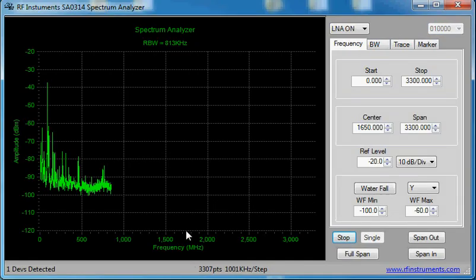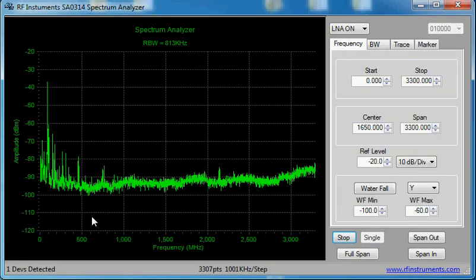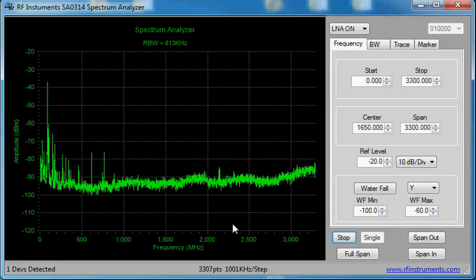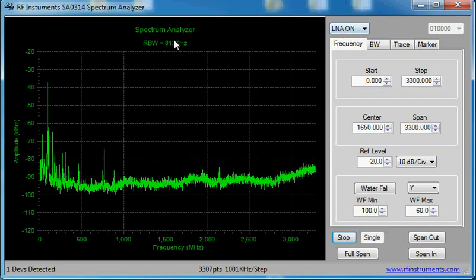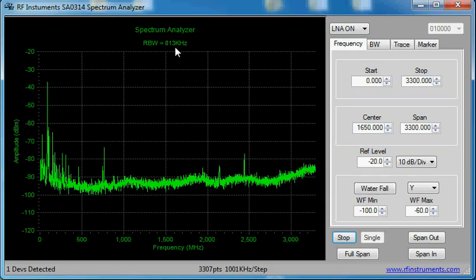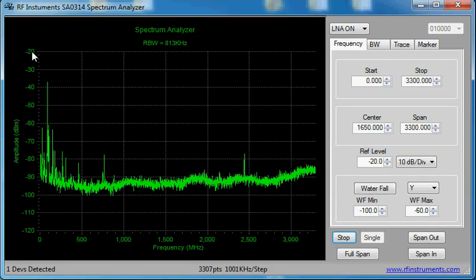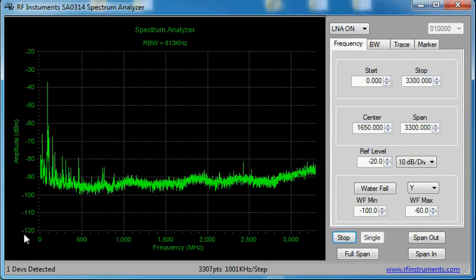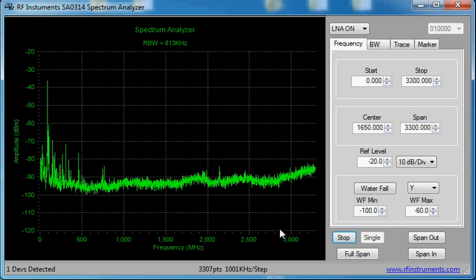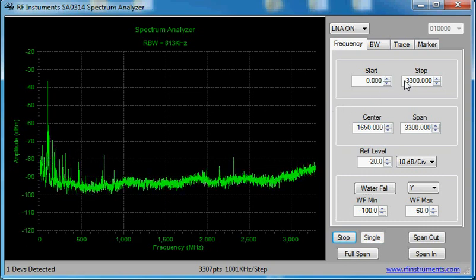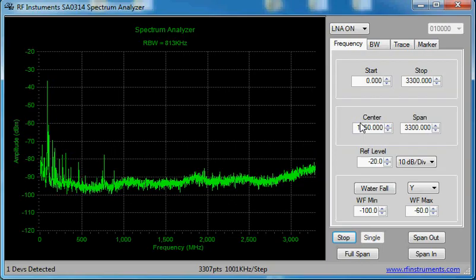The spectrum analyzer will start spanning at full span. The initial conditions are LNA on, receive bandwidth of 813 kilohertz, amplitude of minus 20 to minus 120, full span. You can operate the start and stop, center and span from here.